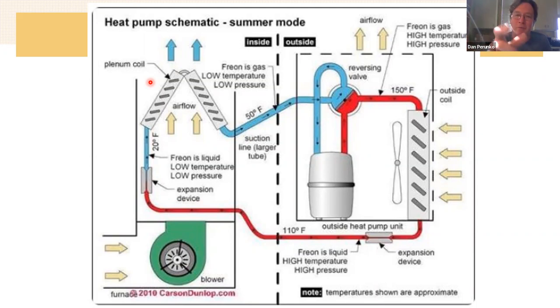That reversing valve, three-way valve that I mentioned earlier. It's right here in this photo. So hot vapor leaves this compressor right here and it gets to that valve and it's pushed into the coil on the outside of the building, which means we're in air conditioning, right? And it cycles around, it's a hot liquid, the pressure is reduced, now it's a cold liquid, then it boils off, now it's a vapor, and it comes back and it's routed like this into the compressor and it gets compressed and heated up. And so the cycle repeats.